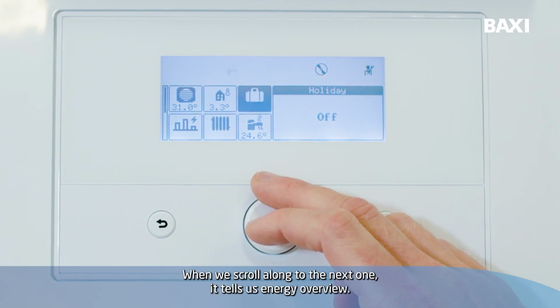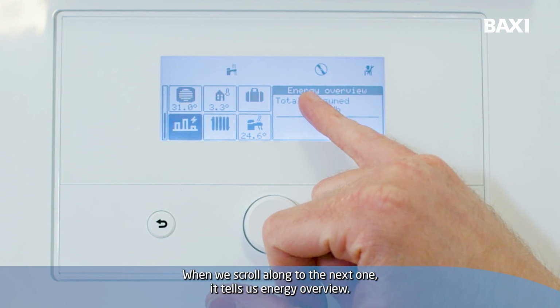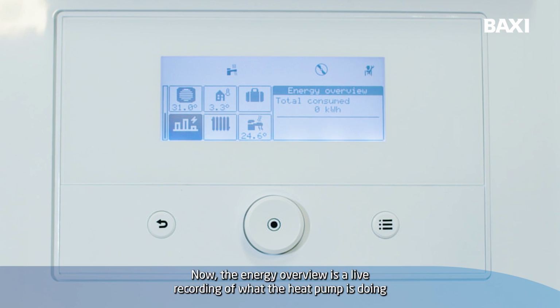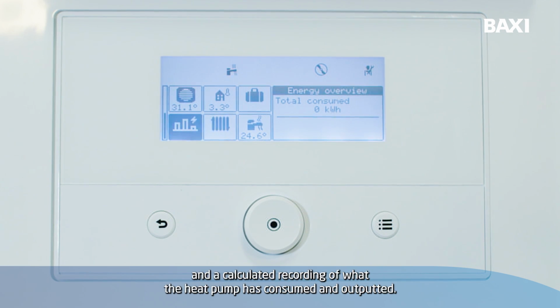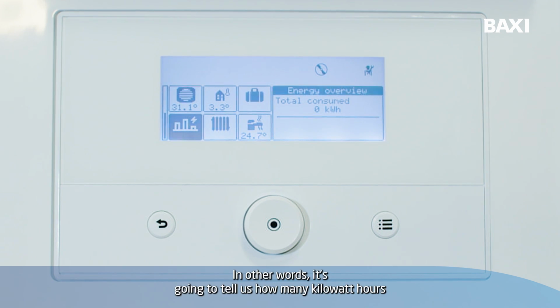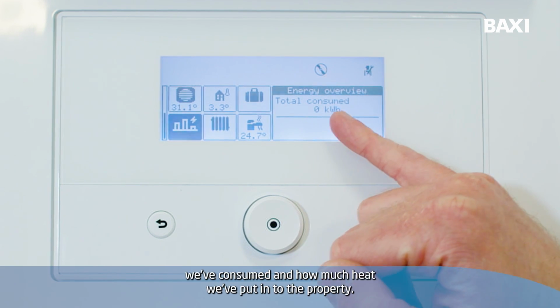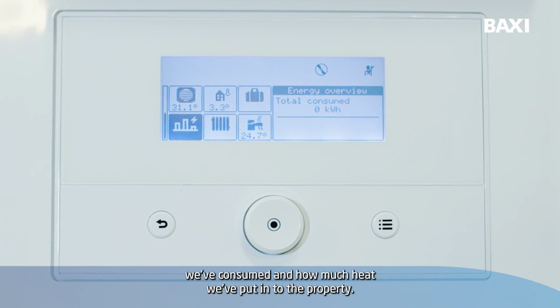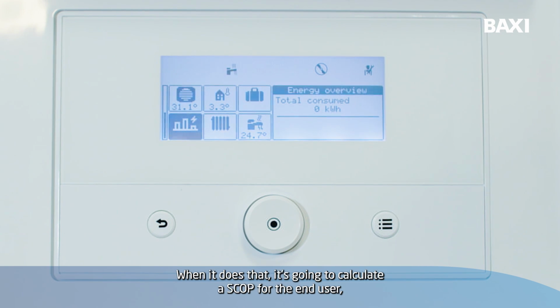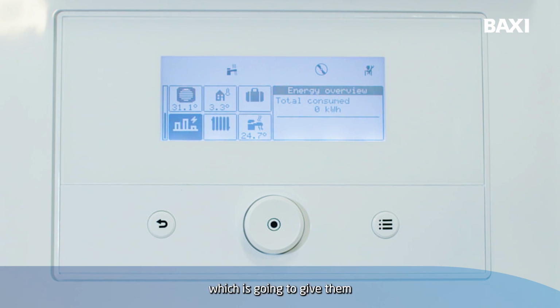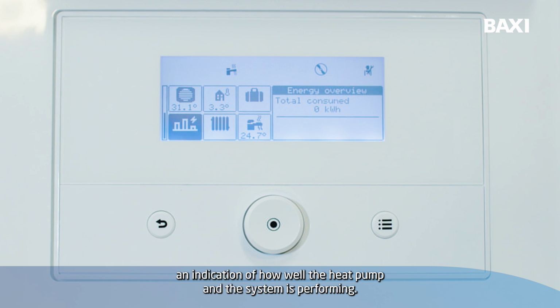When we scroll along to the next one, it tells us energy overview. The energy overview is a live recording of what the heat pump is doing and a calculated recording of what the heat pump has consumed and outputted. In other words, it's going to tell us how many kilowatt hours we've consumed and how much heat we've put into the property. When it does that, it's going to calculate a SCOP for the end user, which is going to give them an indication of how well the heat pump and the system is performing.